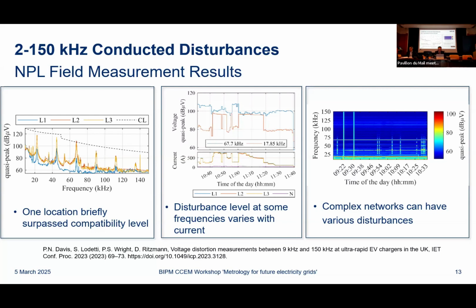And with the quasi-peak, the way it was originally defined is that you take the maximum value over a certain time period. And in this case, we actually found that one of the frequencies, the one in the middle around, I think, 67 kilohertz, briefly exceeded the compatibility level. So this wasn't for a long time. If you look at the plot in the middle, it shows this frequency component over time. And you can see that there's a peak in the middle of the plot where the amplitude of the frequency component briefly increased and then came back down.